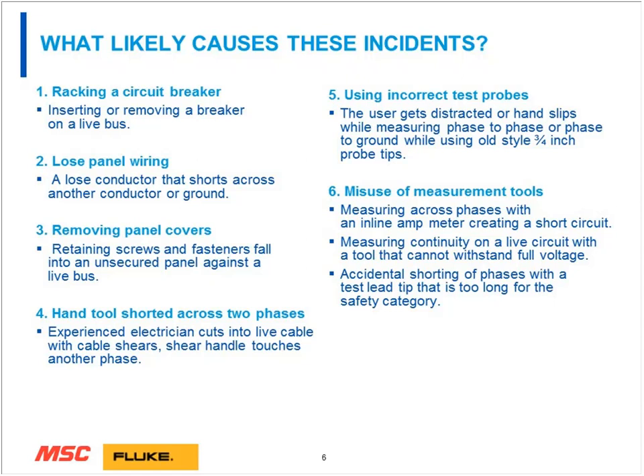Using incorrect test probes. When we looked at that drawing before, anything that's 3/4 of an inch or longer on the end of the test probe could be a source of metallic content or contact for an arc flash. You need to minimize that amount of metal. And also misuse of measurement tools, and we'll cover that in a little bit, of what can happen when measuring in an incorrect mode, causing a short circuit to occur.